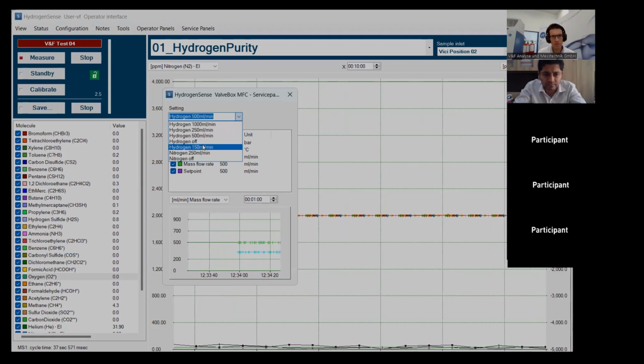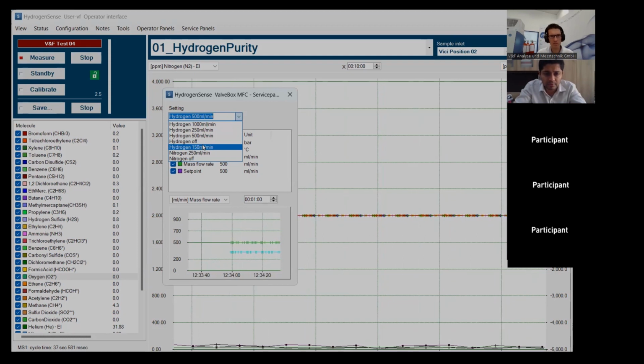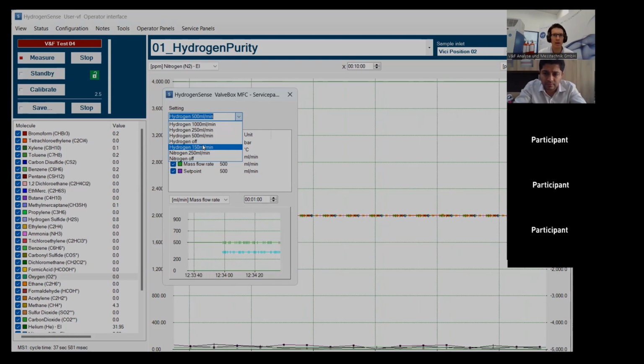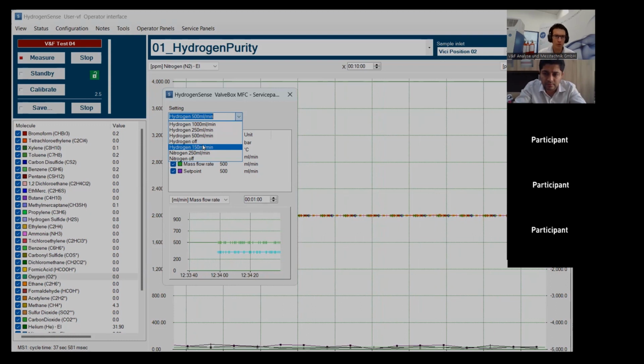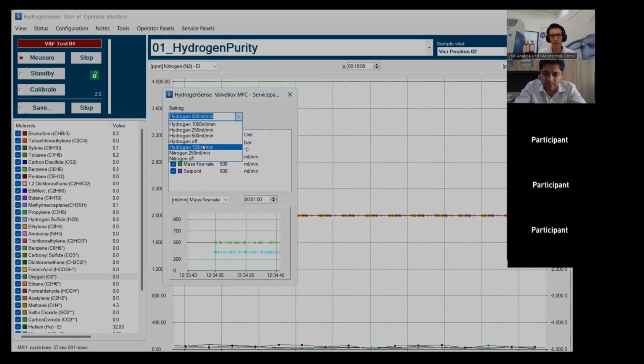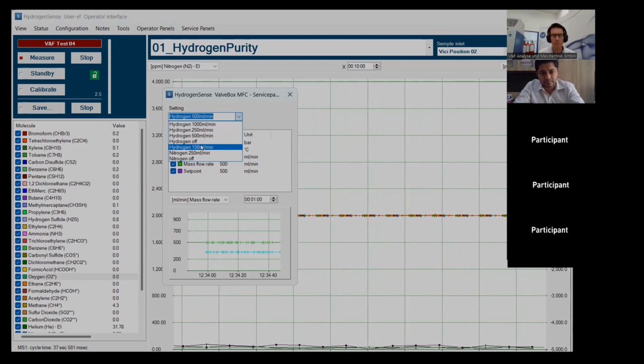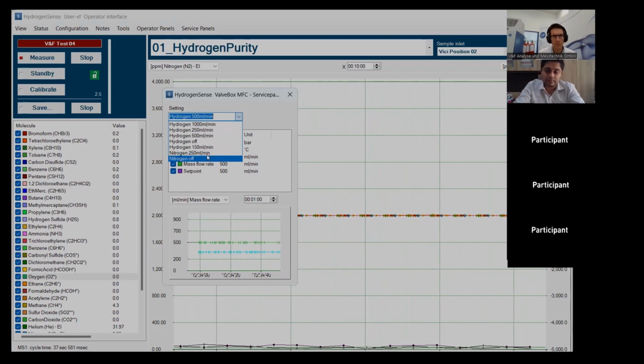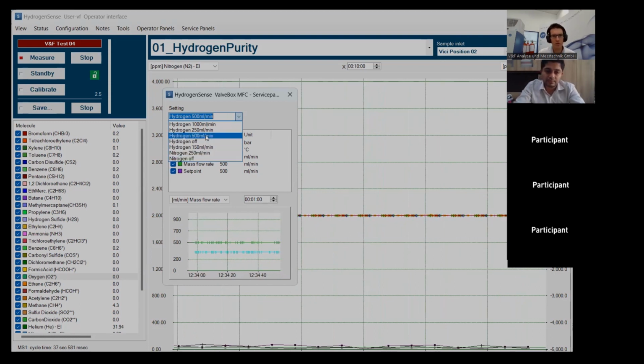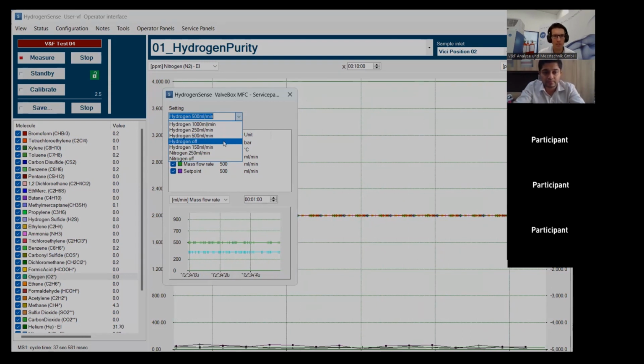So the lowest that I would recommend: due to its vacuum vessels, which always need to be pumped, the instrument is always running, even if you don't do analysis with it. And during that time, I would flush it with a hydrogen 5.0 standard at roughly 150 milliliters. This should be enough for the downtime when you don't use it. And once you switch back into operation and you want to do analysis, I would recommend to go back to 500 milliliters per minute.